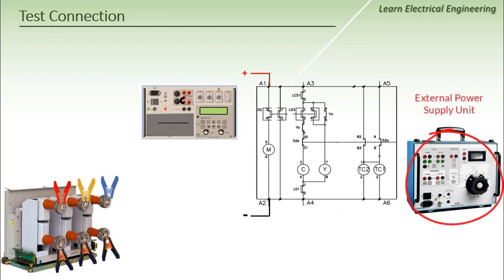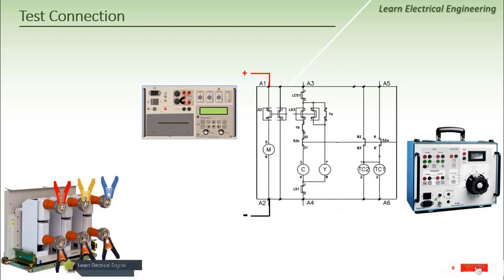Now, how do I get my supply to the close coil and the trip coil? First, I have to disconnect the closing coil from the closing circuit and the tripping coil from the tripping circuit. And so now, with the close coil having both the positive and negative terminals, and the tripping coil having both the positive and negative terminals, the first thing I will do is connect the negative terminal of the trip coil with the negative terminal of the closing coil and connect them to the negative terminal of my power supply unit.